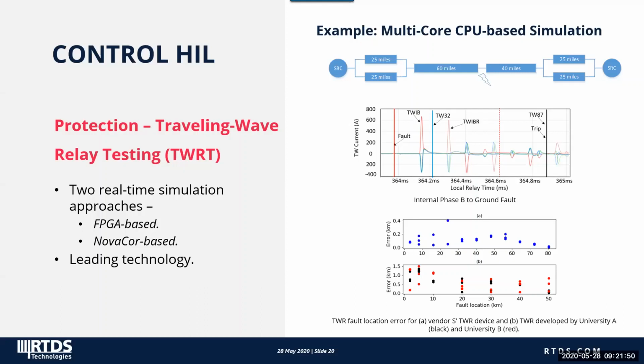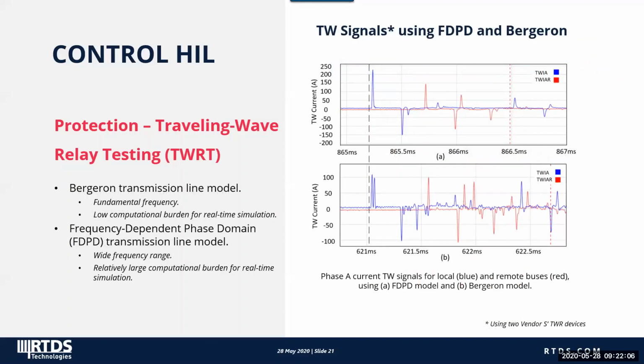The NovaCor-based TWRT solution is capable of simulating larger system representations with a time step of around 2 to 3.5 microseconds, depending on the complexity of the system. Both solutions provide the frequency-dependent phase domain transmission line model, which has been proven to be more accurate to represent the T lines for TWRT applications. So far, RTDS is the only real-time simulator that provides the frequency-dependent phase domain transmission line model and has been adopted by traveling wave relay vendors such as Schweitzer Engineering Laboratories for traveling wave relay testing.